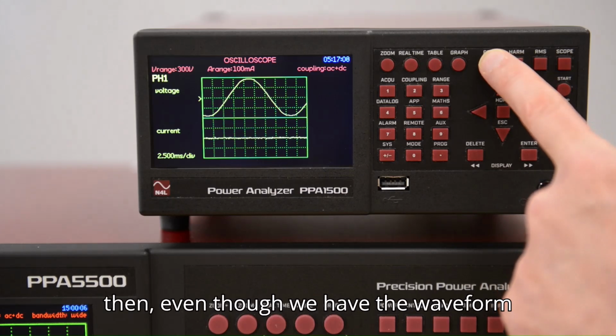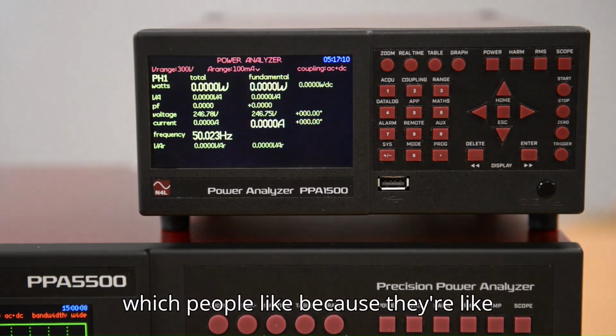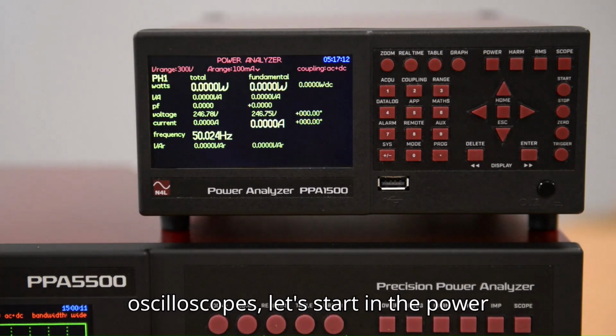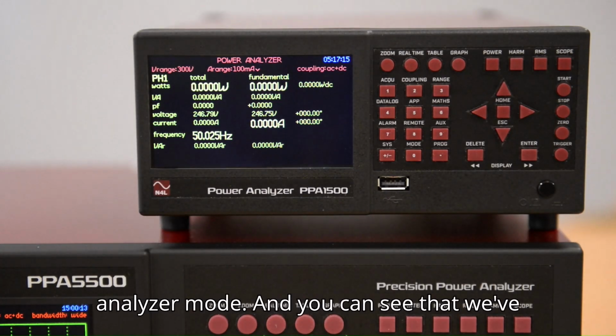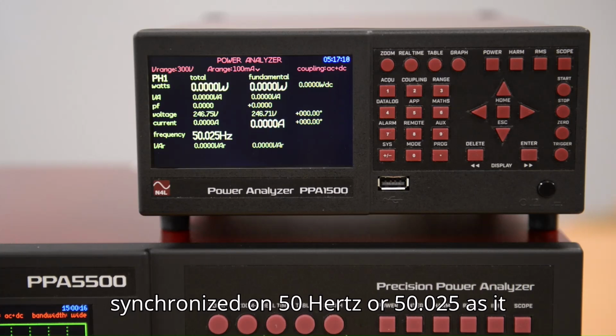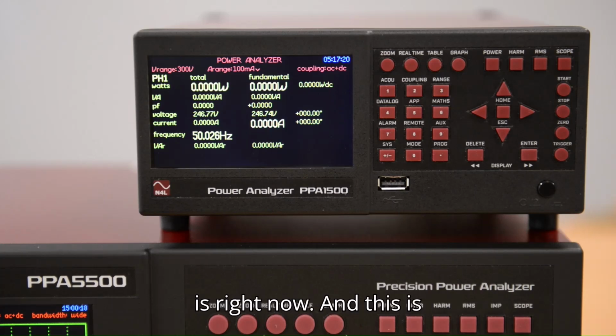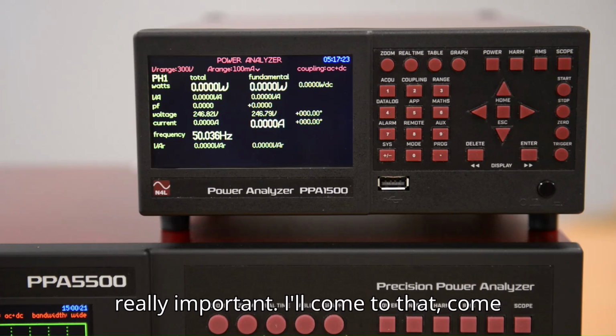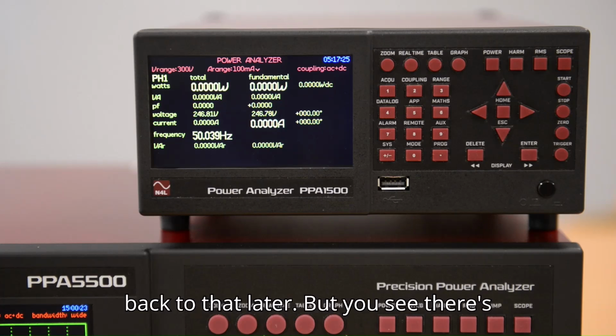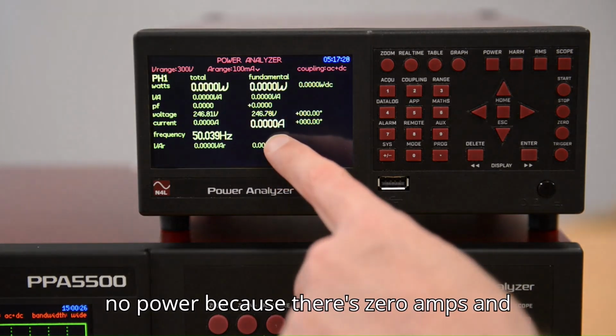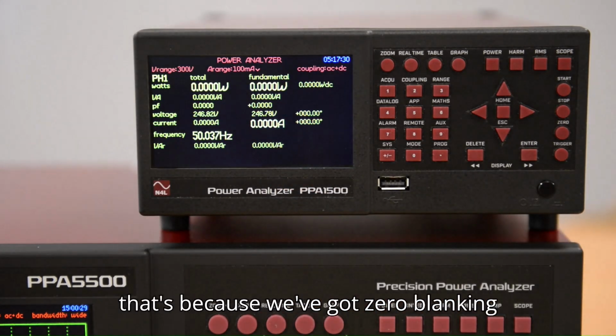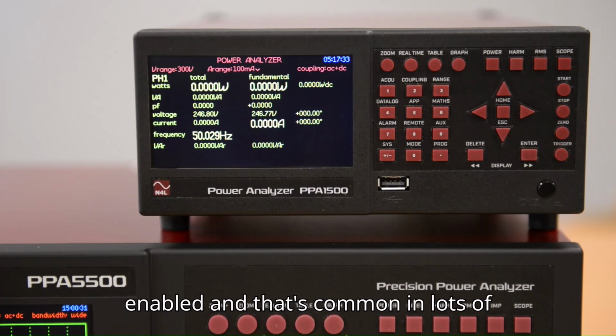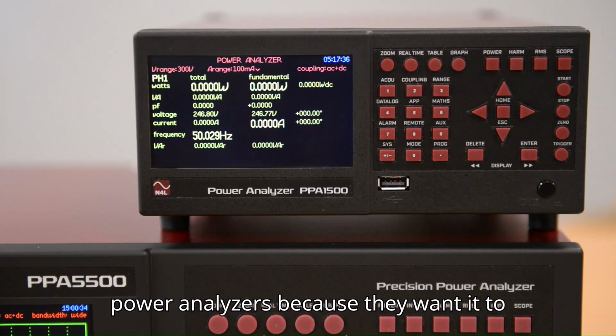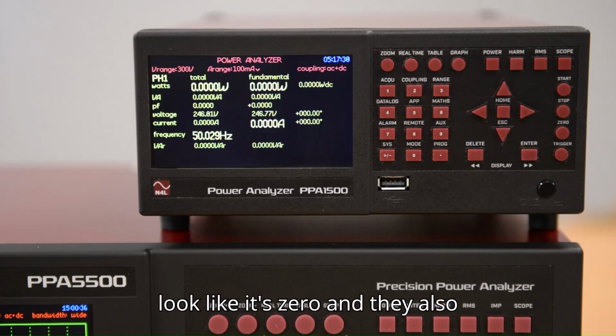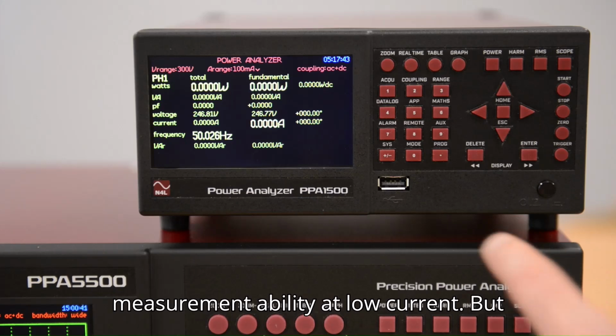But let's start then. Even though we have the waveform, which people like because they're like oscilloscopes, let's start in the power analyzer mode, and you can see that we've synchronized on 50 Hertz or 50.025 as it is right now. And this is really important. I'll come back to that later. But you see there's no power because there's 0 amps. And that's because we've got zero blanking enabled. And that's common in lots of power analyzers because they want it to look like it's 0. And they also hide the absolute resolution or measurement ability at low current.